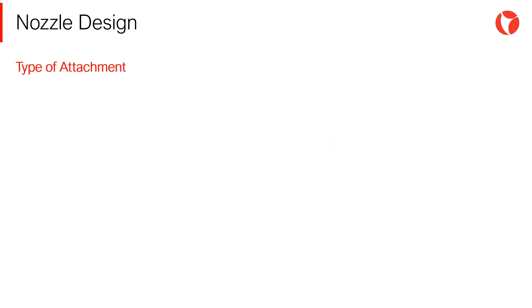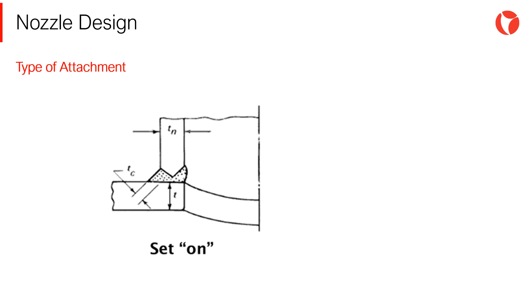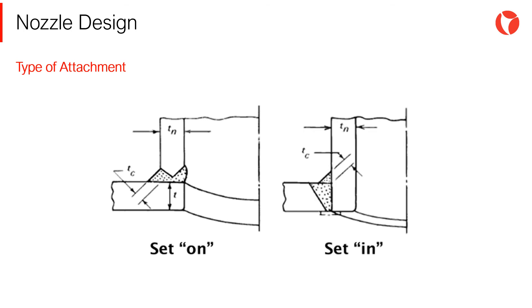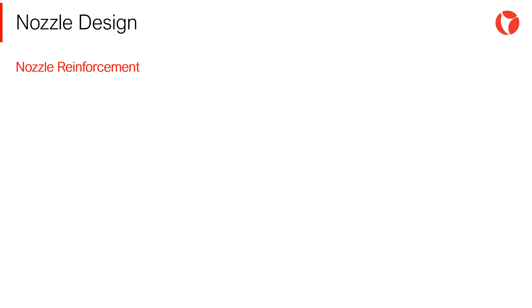Independently from the type of reinforcement, there are two ways to attach the nozzle with the shell or body. Set "on" type: the diameter of the opening in the shell coincides with the inner diameter of the neck, and the nozzle is supported by the shell or head. Or set-in type: the diameter of the opening in the shell coincides with the outer diameter of the neck, and the nozzle passes through the shell or head. This material restoration can be achieved by increasing the thickness of the shell, increasing the thickness of the neck, or adding an external element.